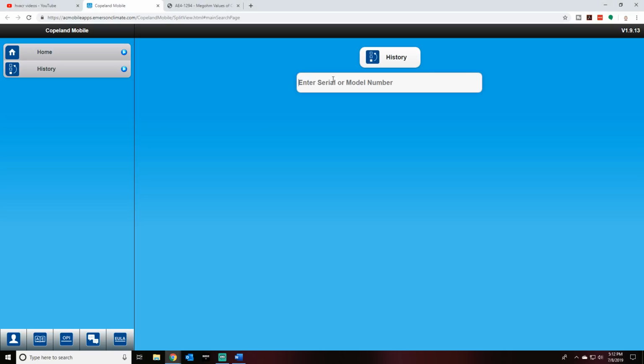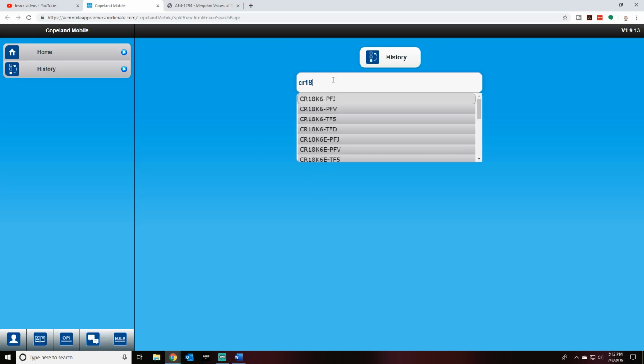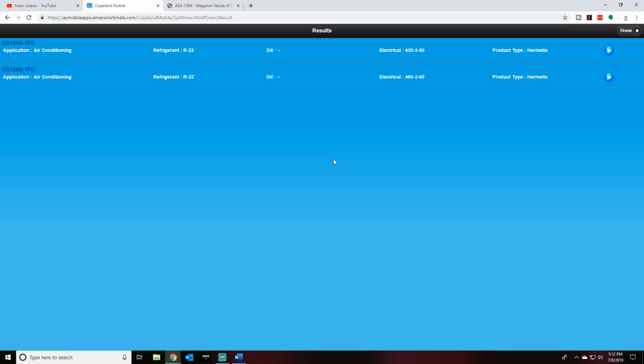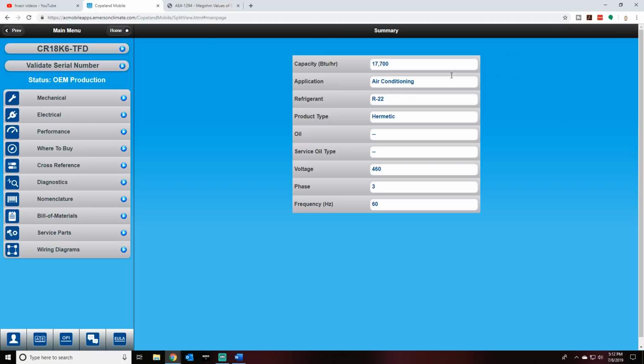What I'm going to do is input the model number. So I'm just going to input a CR18, and you notice that it auto-populates a lot of model numbers. So you need to make sure you find the right one. So we're just going to pick this one, CR18K6. And immediately it pops up and asks you, which compressor do you have? Is it 3-phase 460 or 3-phase 230? One of them's 50 hertz, one of them's 60 hertz. So here in the US, we'd be dealing with the 60 hertz model. So I'm going to click on that.